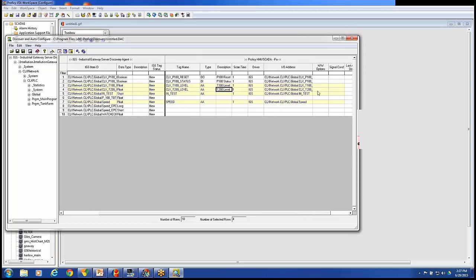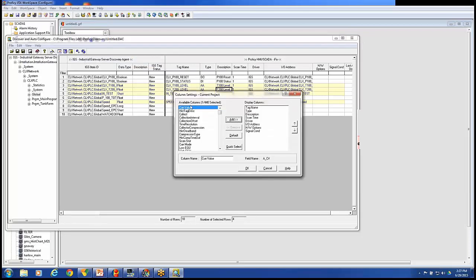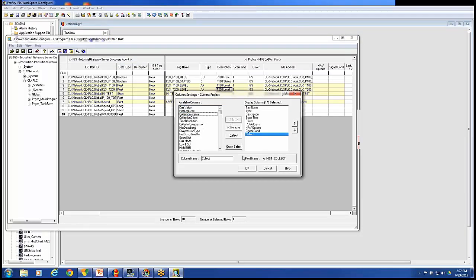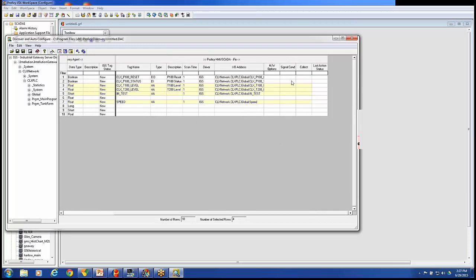I may want to historically collect these. I may want to bring these three in and automatically historically collect them. So I can come under View, go to Target Column Settings, go to Current Project. And I can see iFix settings. One of those is Collect. That added Collect to this list over here. So now if I go in here and put a one by Collect, I will automatically be historically collecting these tags. I'll be setting that setting inside the iFix database. We'll see that in a second. So you can add whatever columns you'd like to manipulate from here.